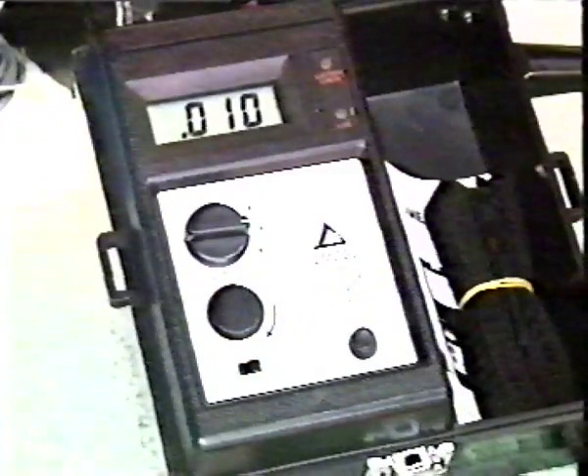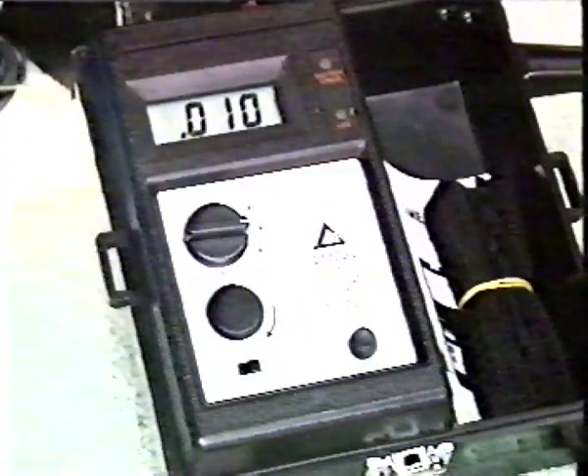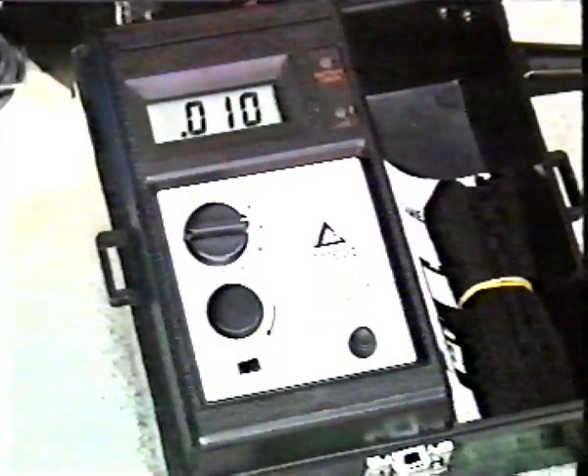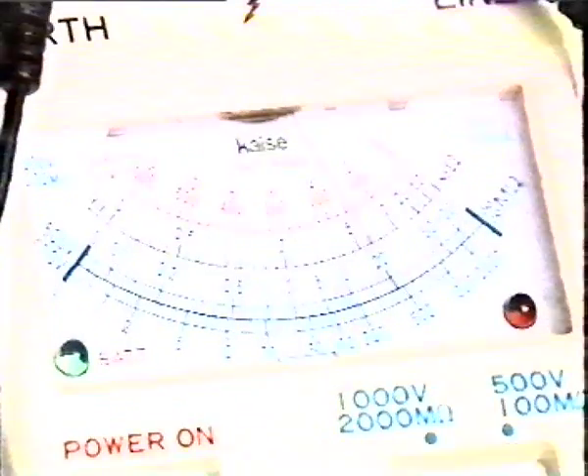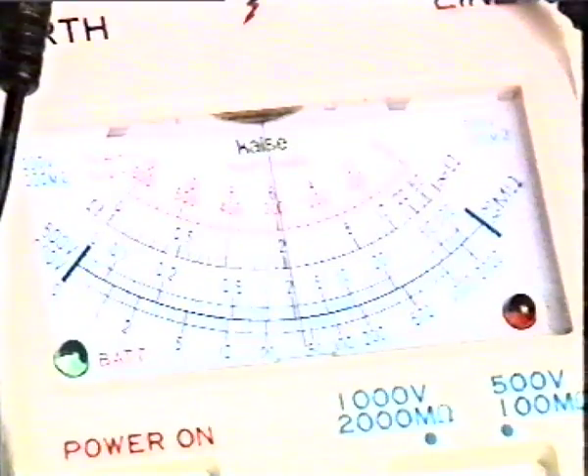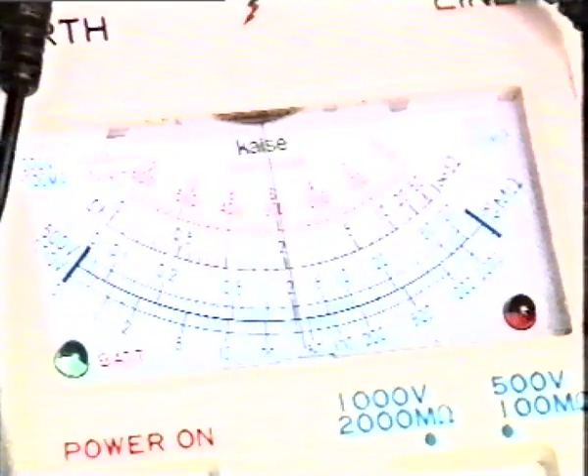Essential test instruments and equipment include an insulation resistance tester and an ohm meter. These may be separate instruments or a single instrument incorporating both functions. Both digital and analog types are available, and the choice of which type to use is left to personal preference. However, if an analog type ohm meter is used, it's recommended that it should indicate 2 ohms at not less than 25% of full-scale reading.